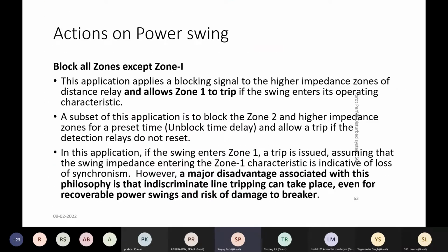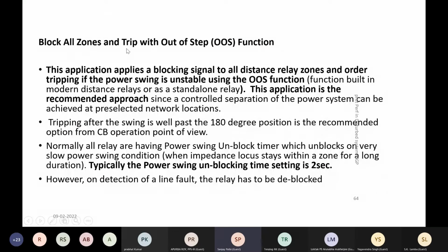So the second option is to block all the zones and trip with the out of step function. This was the recommendation given after the 2012 grid collapse, that you should not block only zone 2 and zone 3, but block all the zones, and then there is a separate out of step protection function in the modern distance relays. You use this function either to trip this line which is being protected, or to separate the system by mode tripping. So this out of step function is one of the methods of, you can say, controlled isolation of an area or a power station in a manner so that there is generating station survival along with some load.